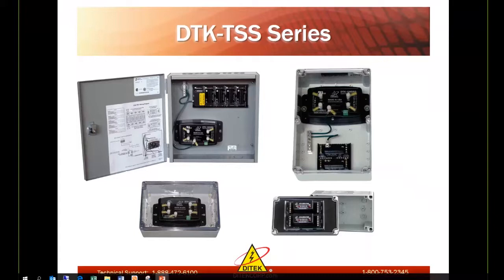Down below the TSS2, we offer the TSS3. That device is typically used at remote locations. It will protect up to 4 pair. It's a single point ground, of course, and that is a NEMA 4X enclosure. That's perfect for SLC circuits on building to building runs. We also offer the TSS4D, which is to the left of that. That is our series device in a NEMA 4X enclosure. Typically water departments and high corrosive atmosphere environments will utilize that product.